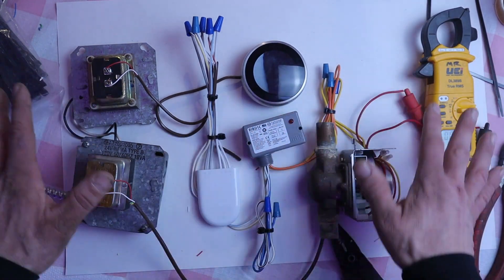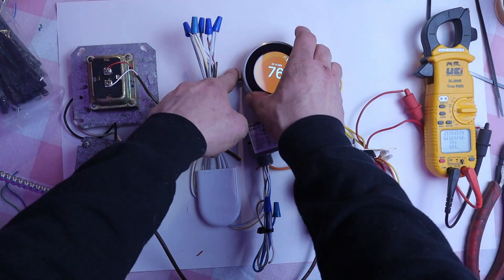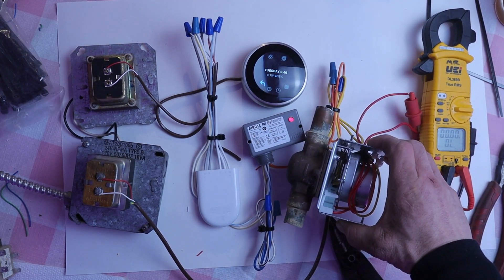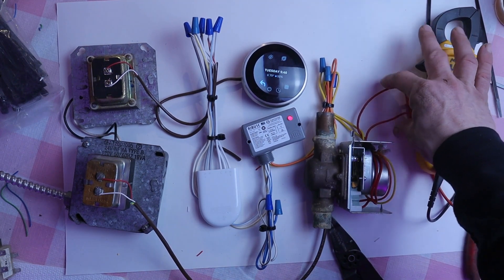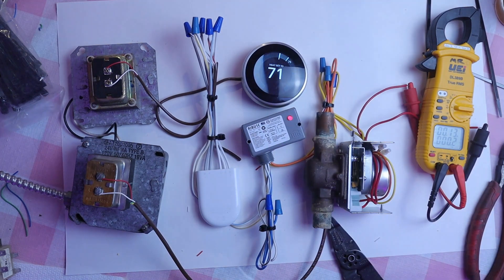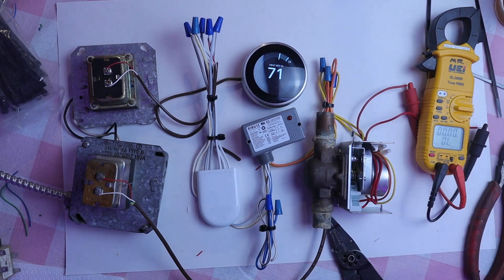I have everything powered up here — the burner switch is on and the thermostat is working. I'm going to call for heat, which will activate this relay. The relay is going to operate the zone valve — you can see the motor move in there. Then we're going to have continuity on our multimeter, which tells us the T-T circuit is activated and the boiler will fire up. I'm going to shut this down and the same thing will happen in reverse: the relay deactivates, the zone valve unpowers, the motor closes up, we lose continuity, and the boiler shuts down.